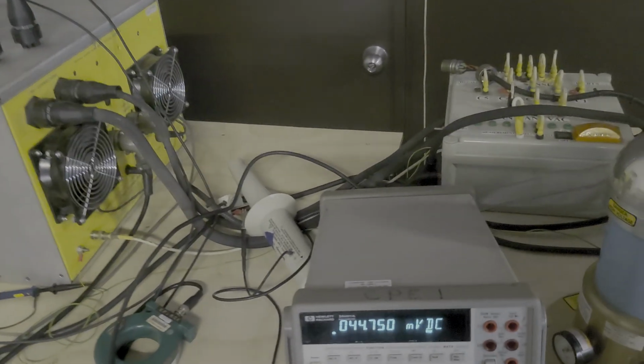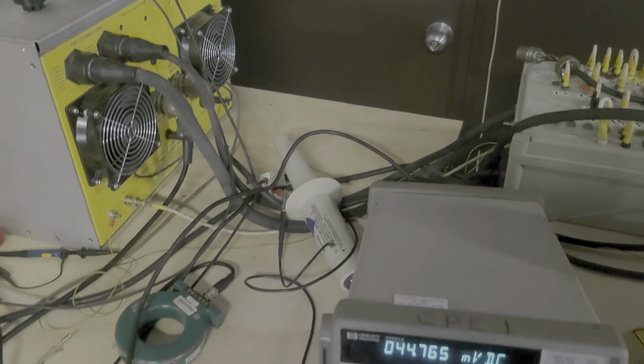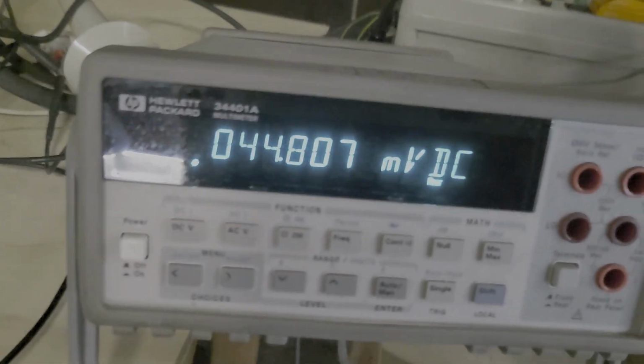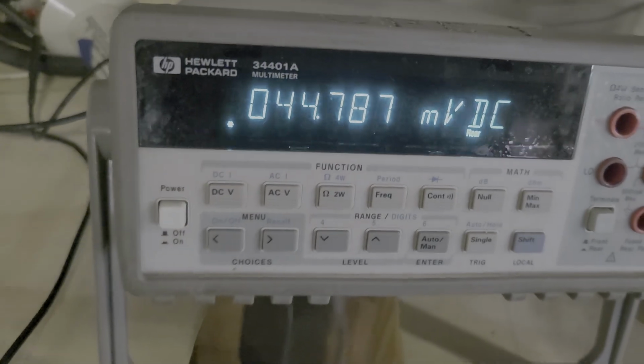Alright, so it took a couple iterations, but I finally got it to output on the pulse top supply at 100% duty. And you can see I have about 45 volts, which is what we read on the GUI. 44.79. I'm going to write down 44.79. And I'm going to adjust offset until we read that, which we are reading exactly 45.0. So we need to bring offset up. 44.79. Approximately there. 44.787.